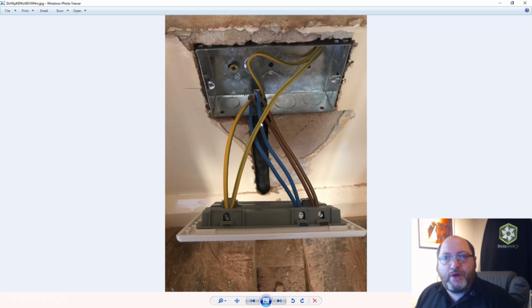Imagine if this back box, you see these 20 mil knockouts here, imagine if the wiring system was a steel conduit system, and the steel conduit system itself was being used as the protective conductor. So there was no individual protective conductor cable, the wiring system was the protective conductor itself. Well, the socket outlet would require a connection to the protective conductor, and that is, in my view, what this terminal is for. So the earthing would come up a steel conduit, it would then go into the back box, and we need to use the terminal to bring the earth forward into the socket outlet.